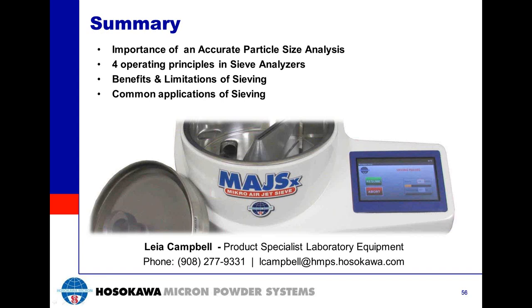Jenny asks: what analysis method is the most accurate? It depends on the target of your scope and material being analyzed. For sticky cohesive materials, consider wet sieving. For nano-sized materials, consider laser diffraction. For particles between 4,750 microns to 20 microns, air jet sieving may work best. Will asks: is this product suitable for use with explosive powder? Our machine is not designed for explosivity, so that would be one of the safety precautions to consider.